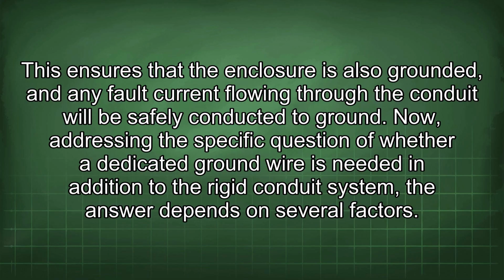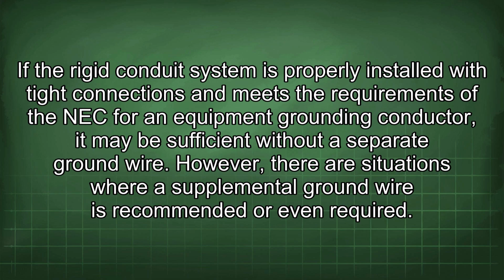Now, addressing the specific question of whether a dedicated ground wire is needed in addition to the rigid conduit system, the answer depends on several factors. If the rigid conduit system is properly installed with tight connections and meets the requirements of the NEC for an equipment grounding conductor, it may be sufficient without a separate ground wire. However, there are situations where a supplemental ground wire is recommended or even required.